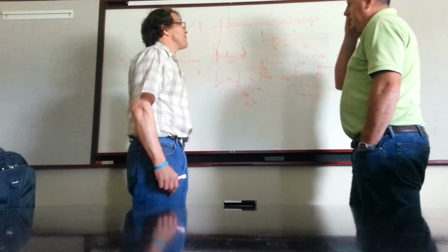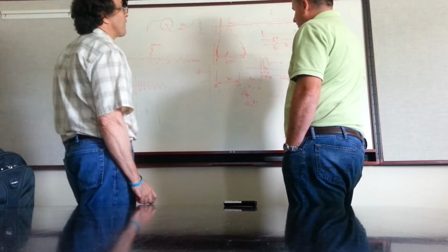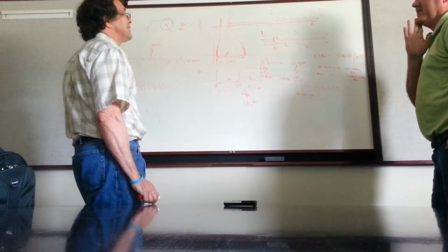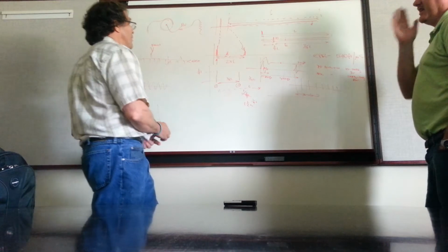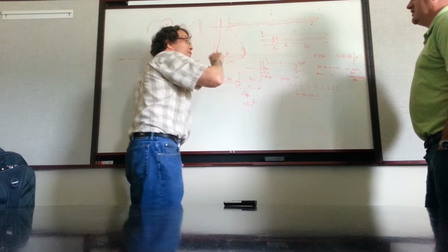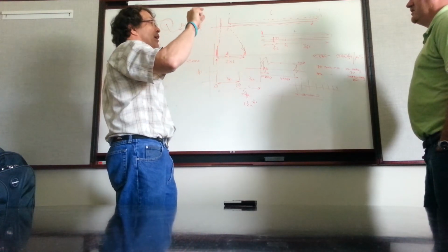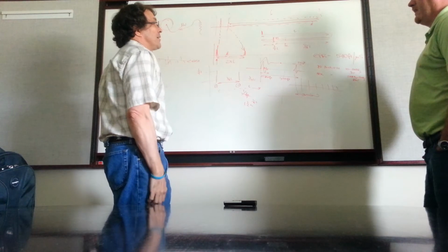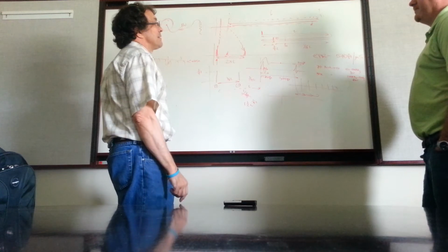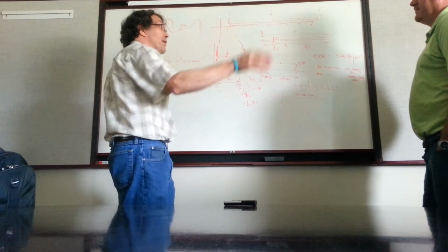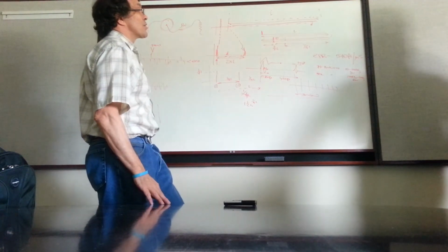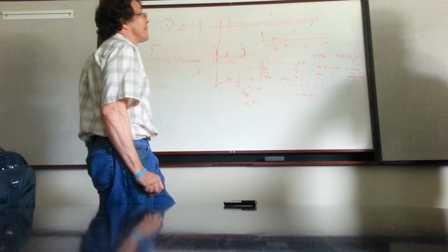Right. So then, were we thinking backwards yesterday? Because I'm still bothered by that 10,000 foot reel that we had yesterday. It was chopped in half. Well, we brought it back, saw the fault, we were thinking the fault was right here. So that means the fault was very close to the non-powered end, which in our case was the top of the reel. So if they took the top of the reel, because we were lapping off the top, weren't we? And we got rid of one fault. So if it was the top of the reel, because it's the non-powered end, why didn't it pass when we brought it back?